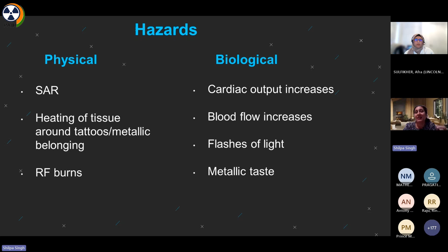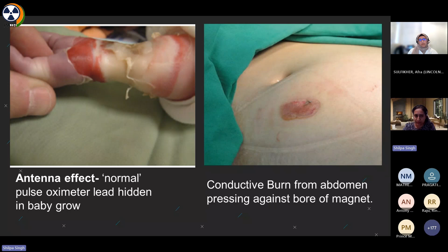So here I have some examples. As you can see, this is called the antenna effect. There is a pulse oximeter which was hidden, and this burn has become so severe that it has turned into a third-degree burn. Another thing, a conductive burn from the abdomen pressing against the bore of the magnet. Pressing against the bore of the magnet, that is why there were non-conductive foam pads placed between the patient and the bore. This is called a proximity burn.